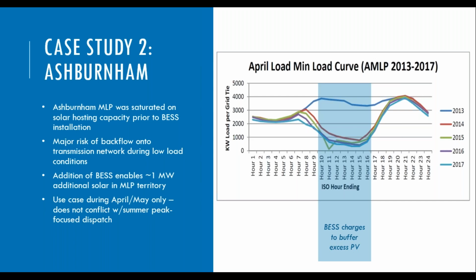They found that putting in this battery, which is mainly used for peak avoidance during the coincident peak hours, both monthly and for the overall ISO system in the summer, enabled them to increase their hosting capacity by about a megawatt throughout the MLP territory. What's really interesting about this use case is that it's only during April and May that they're concerned about this, so it doesn't conflict with a summer peak focused dispatch strategy, which is really the economic driver.